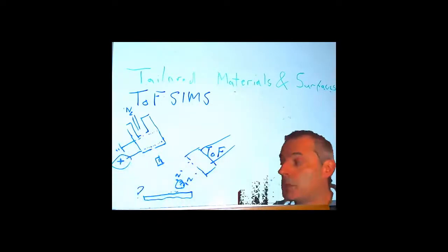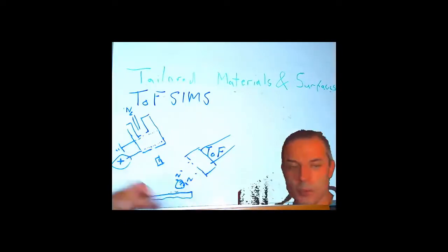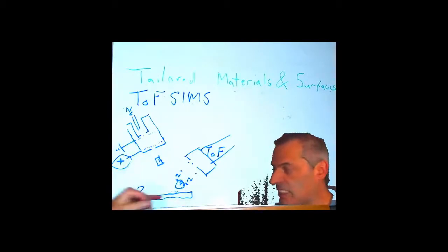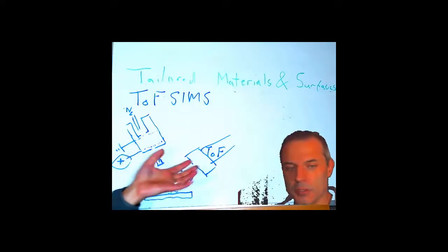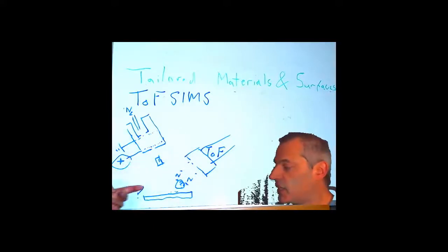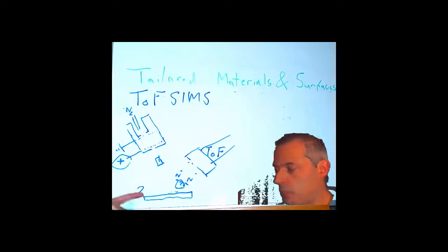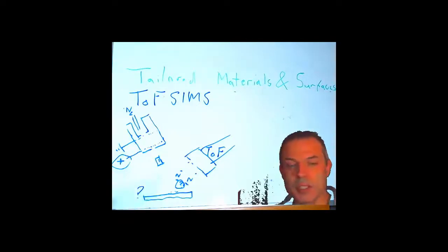So this technique is particularly sensitive, particularly surface sensitive. It only goes a few atoms into the surface. It doesn't damage the surface very much at all. It is actually knocking off atoms from our surface and sucking them into our spectrometer, but we're counting them individually, so we don't need very many. And that means that our sample is barely damaged by this. It's less damaged than if we scratch it with a cloth. It does mean it's very difficult to prepare the sample beforehand, because if it's dirty, if we've touched it with a fingerprint, all we will see is fingerprint.